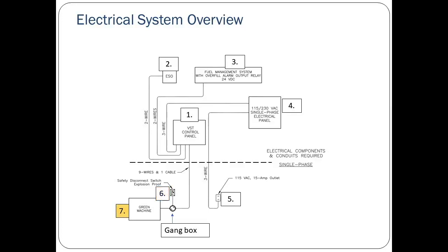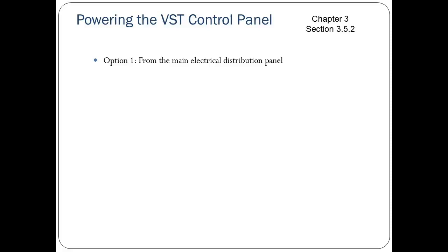Number 7, and finally the green machine itself. The green machine is the vapor processing unit. Before talking about pulling any wires, it is important that you, the electrical contractor, decide how to provide power to this electrical system. There are 2 options for powering the VST control panel. Follow along in section 3.5.2 of the manual. Option 1, from the main electrical distribution panel, or Option 2, from the station emergency shutoff relay.